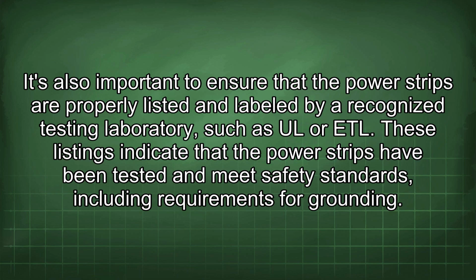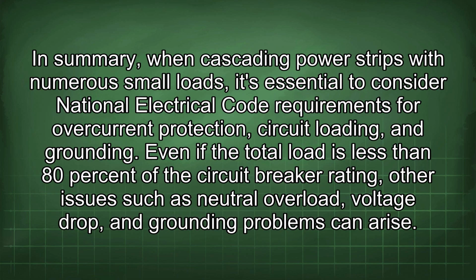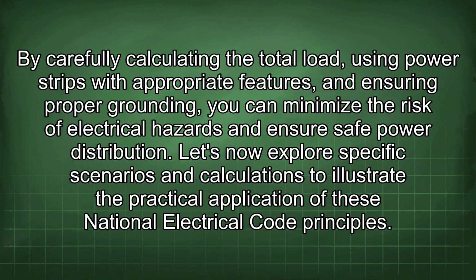These listings indicate that the power strips have been tested and meet safety standards, including requirements for grounding. In summary, when cascading power strips with numerous small loads, it's essential to consider National Electrical Code requirements for overcurrent protection, circuit loading, and grounding. Even if the total load is less than 80% of the circuit breaker rating, other issues such as neutral overload, voltage drop, and grounding problems can arise. By carefully calculating the total load, using power strips with appropriate features, and ensuring proper grounding, you can minimize the risk of electrical hazards and ensure safe power distribution.